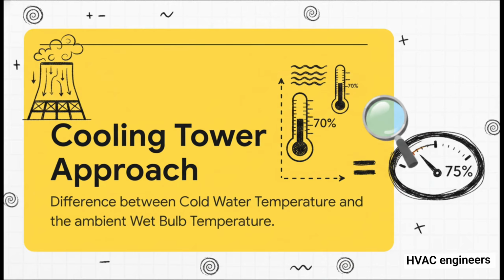In a perfect, mathematically ideal world, your cold water temperature would exactly match the wet bulb temperature of the outside air. That is simply the lowest temperature achievable solely by evaporating water. But in reality, achieving that 100% efficiency would require an infinitely large tower and would cause massive water evaporation losses. It's practically impossible. So the real-world goal, the sweet spot engineers aim for, is hitting a practical efficiency of about 70 to 75%. That's where the math actually meets industrial reality.